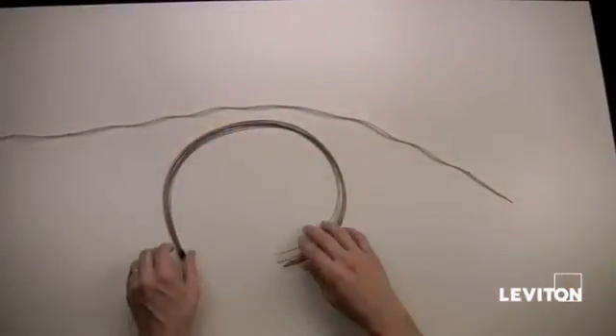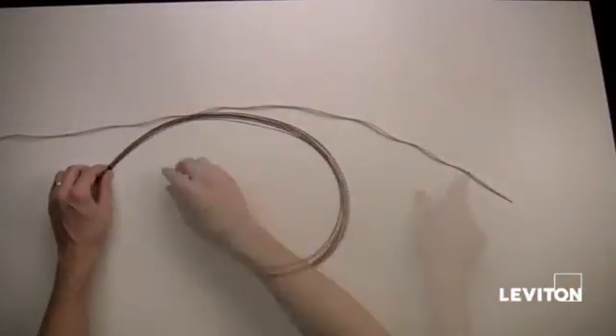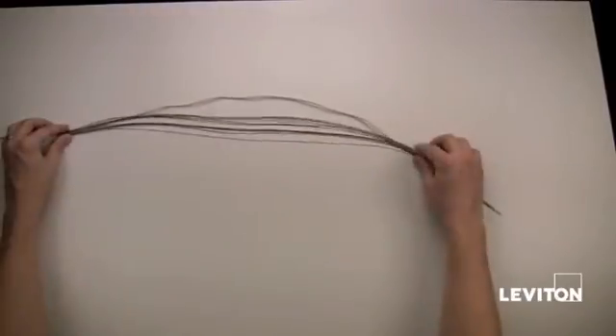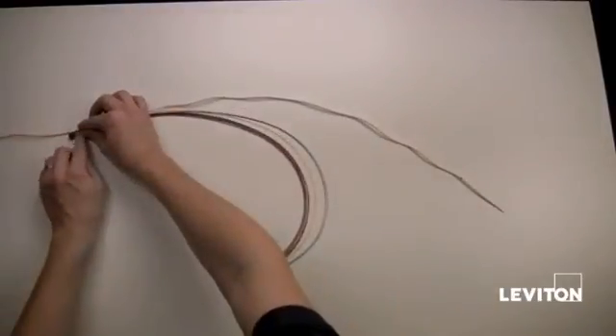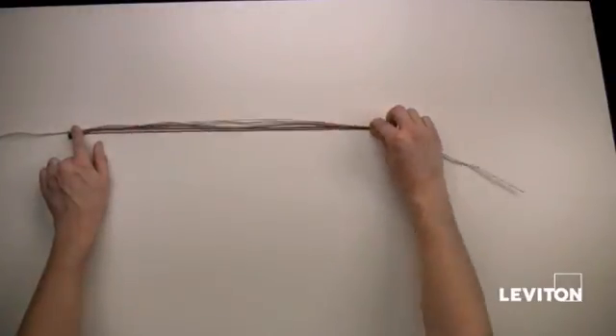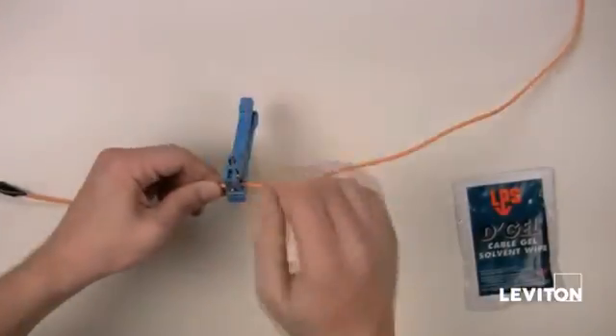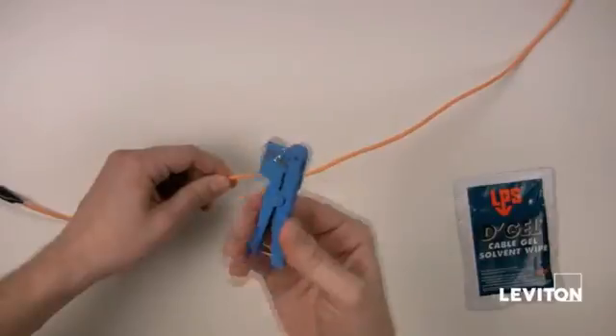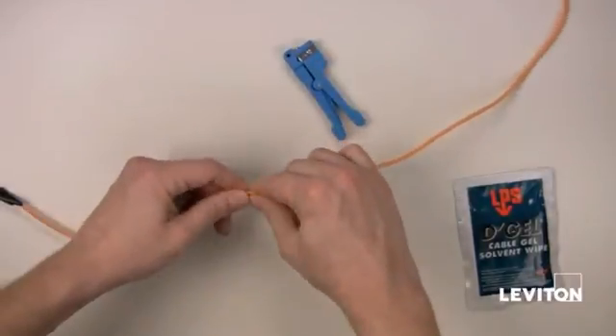Measure the first fiber tube back 3 inches longer than your fan out tube. Make a mark at the terminal assembly, and then score and strip exposing the 250 micron fibers inside the buffer tube.